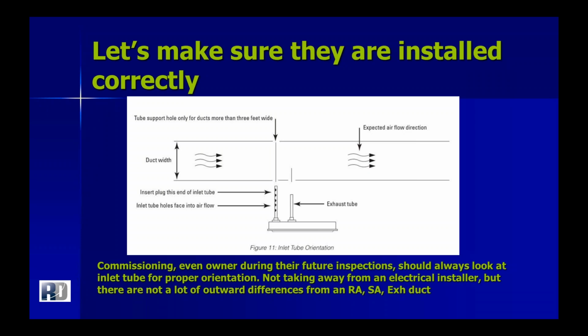So one thing we just wanted to throw out there is that we're not talking about these devices having a construction verification sheet or a functional test sheet associated, because I believe we would all understand, for what we likely provide as our services, that there would be a construction verification sheet and a functional test. So we're really not getting into the nuts and bolts of that. But let's make sure that our duct detector is located properly within the duct. And the reason we indicate this is that really all ducts, especially during construction, virtually look the same.